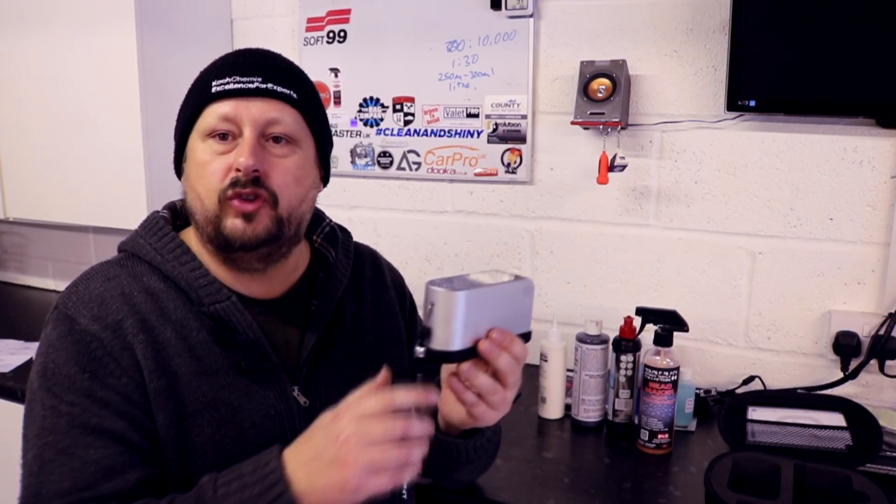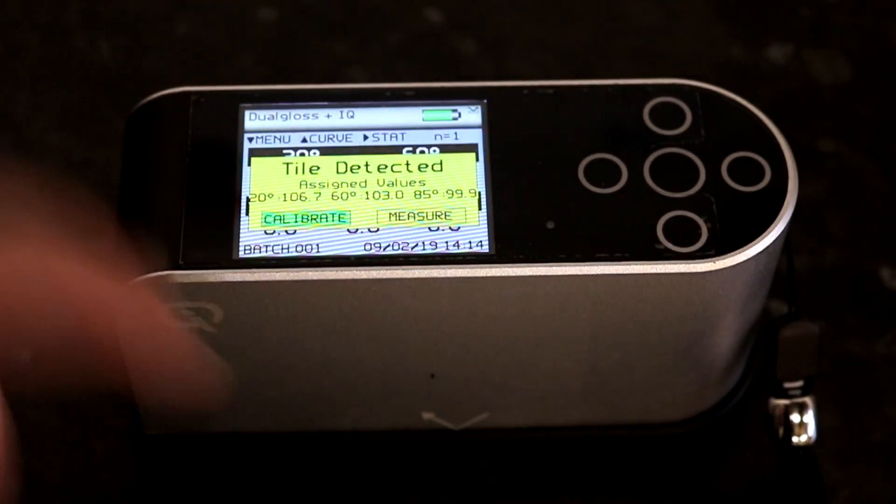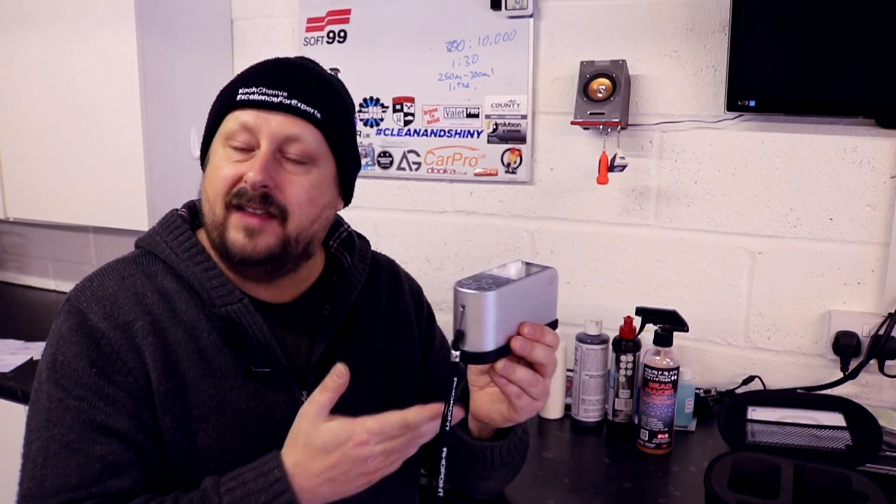The device is very simple to use. You turn it on, and it detects whether the calibration plate is attached. If it isn't, you can take readings on the previous calibration. If it is, it will ask you to either calibrate or just take a measurement — you don't have to calibrate every time. However, Rhopoint advise calibrating at least once per day, and then you're good for the whole day. The calibration plate is high quality — glass or marble — and comes with a signed certificate guaranteeing its gloss value, which is critical because a cheap calibration plate would throw off the whole machine.